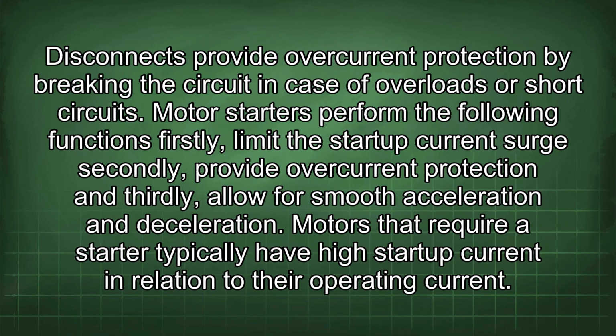Motor starters perform the following functions. Firstly, limit the startup current surge. Secondly, provide overcurrent protection. And thirdly, allow for smooth acceleration and deceleration. Motors that require a starter typically have high startup current in relation to their operating current.